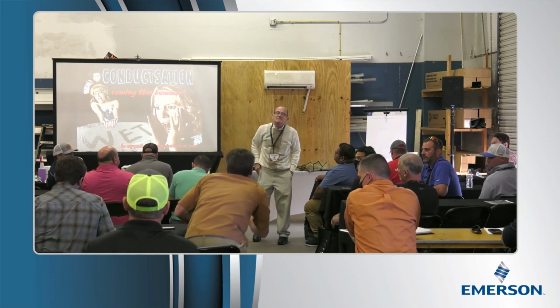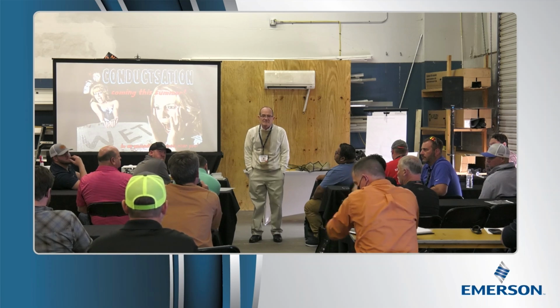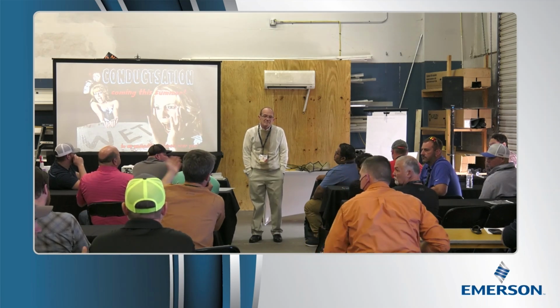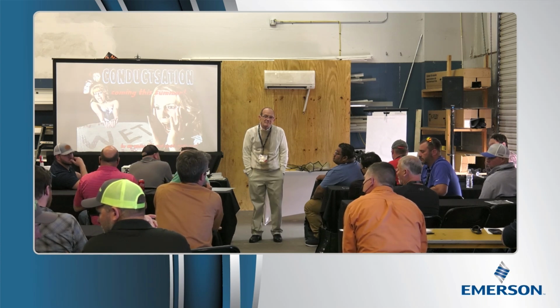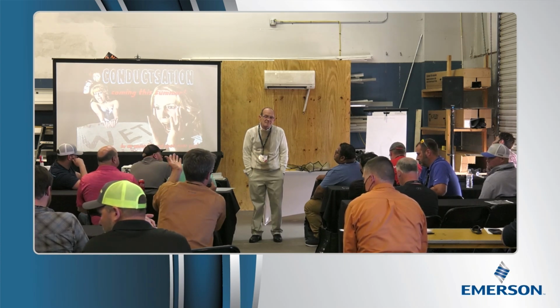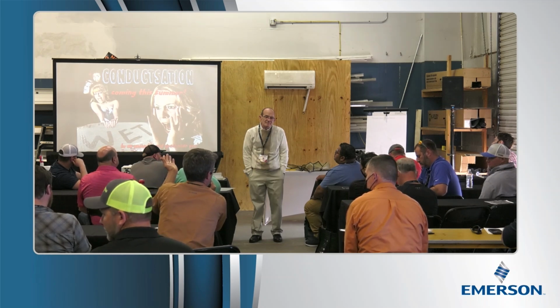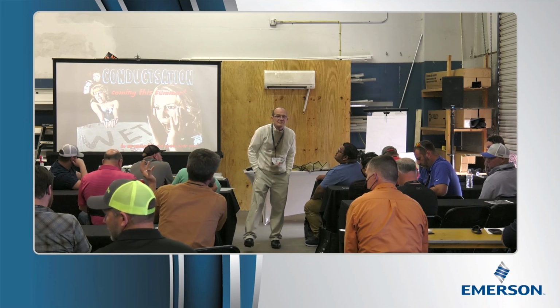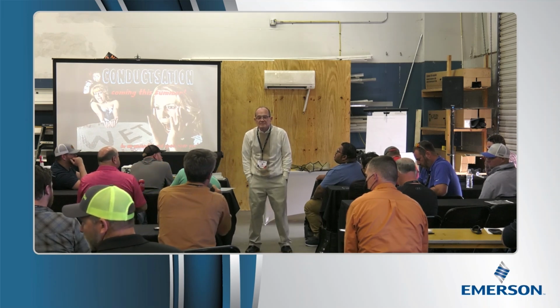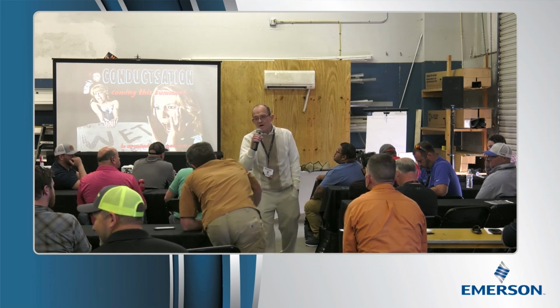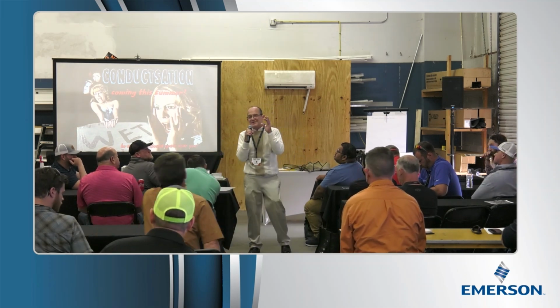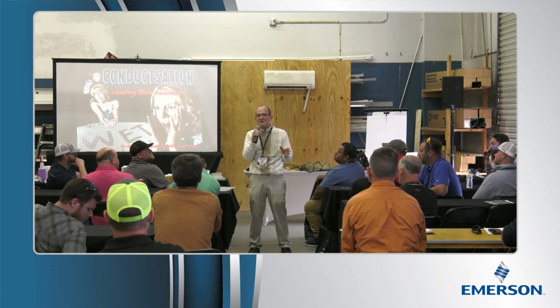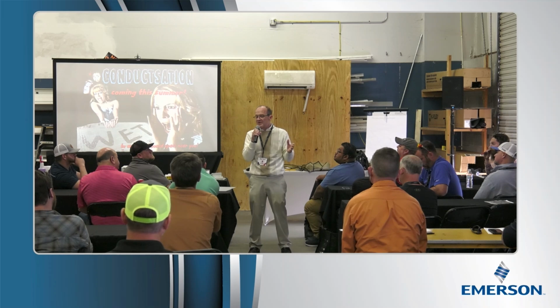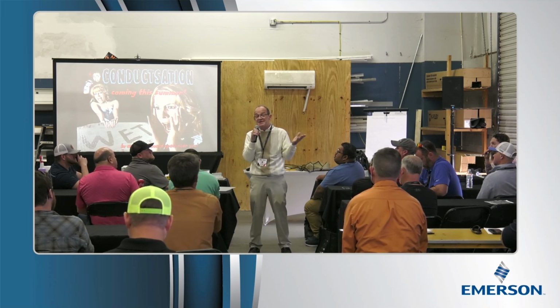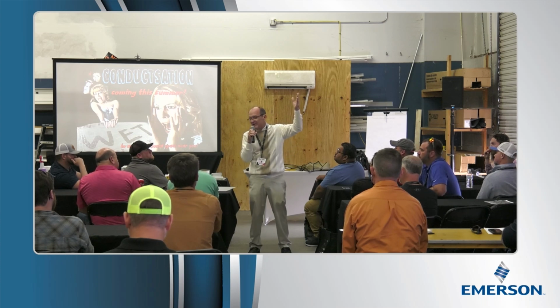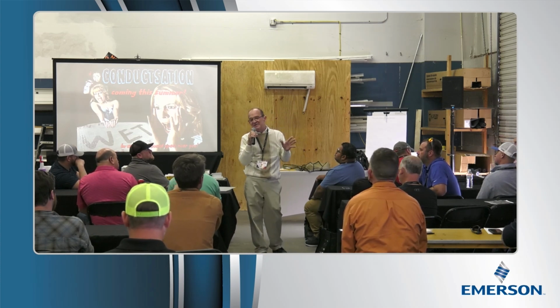Inside of supply plenums, we'll tear out duct board or duct liner, supply plenums, black mold, condensation obviously going on inside of there. You have high relative humidity upstream of the evaporator coil. Maybe migration, anyway, that kind of thing. The only thing that can make that happen, there's one building component that is perfect for condensation: it's called an evaporator coil. There is no other component in the building that is an appropriate place to condense moisture, maybe on top of the roof, but we don't want to condense moisture into any other building materials, including duct board.